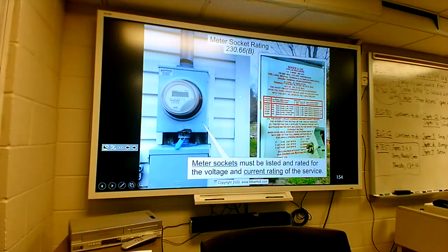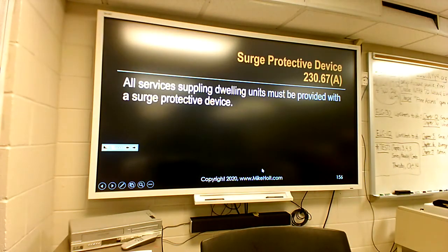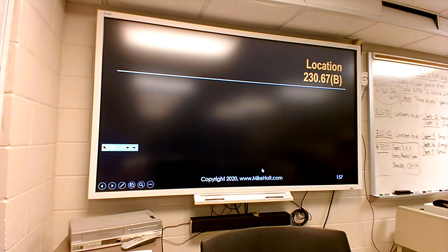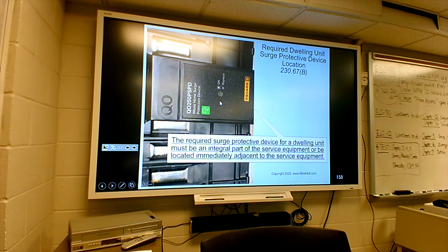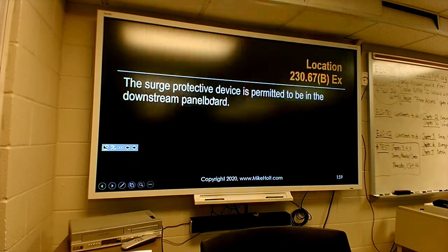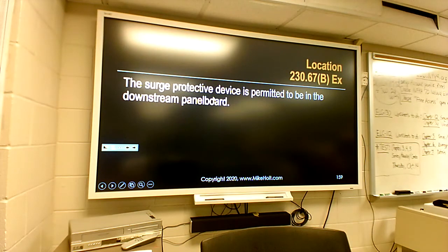Meter sockets. Meter sockets must be listed and rated for the voltage and current rating of the service. Surge protection. All services supplying dwelling units must be provided with a surge protective device. Now this is one that actually snaps in where a breaker would snap in, on the load side. It must be an integral part of the service equipment or be located immediately adjacent to the service equipment. So that's the type that can actually be snapped into the panel like a breaker. It's permitted to be downstream, in the panel board, so that's where you can have those in breaker positions.